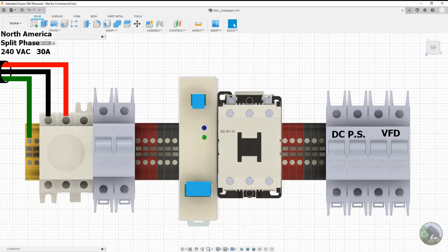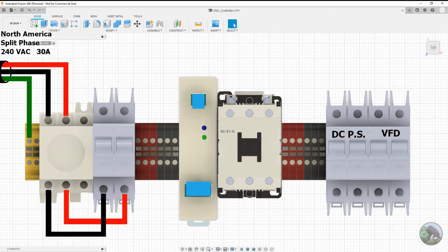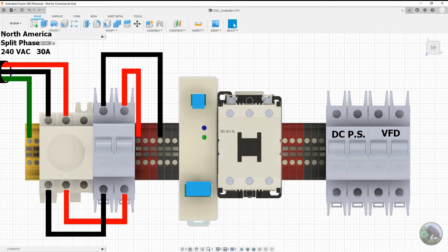And so if we turn on and thus close the rotary disconnect, power then is fed to the circuit breaker right next to it. This is a 30 amp circuit breaker with a C tripping curve, and this just mimics the rating of the circuit breaker at the panel in my house. And hopefully this one's a bit better quality, so it's just here as an added piece of safety. And so when that circuit breaker is closed, power is fed to the distribution bus right next to it.